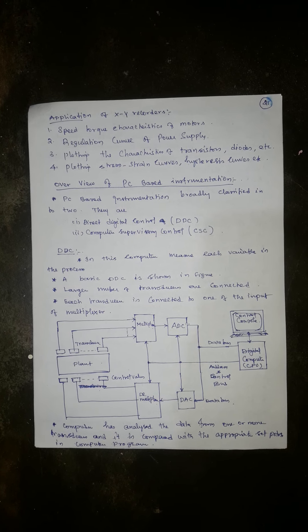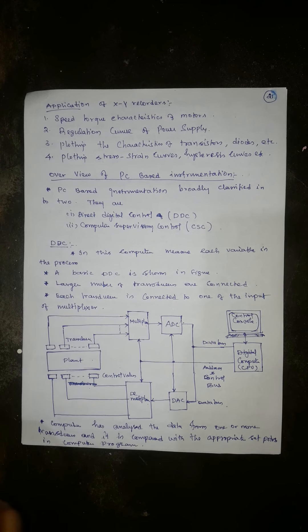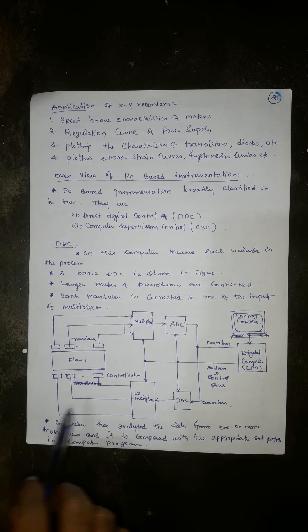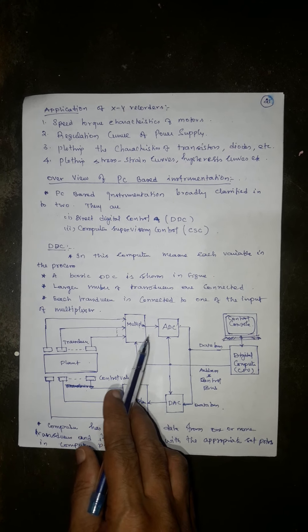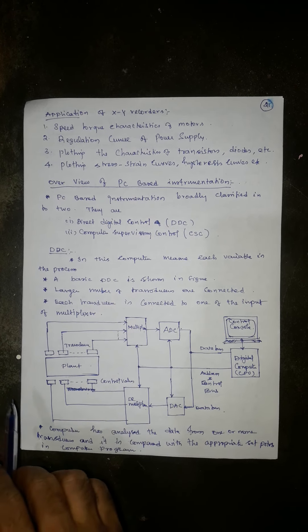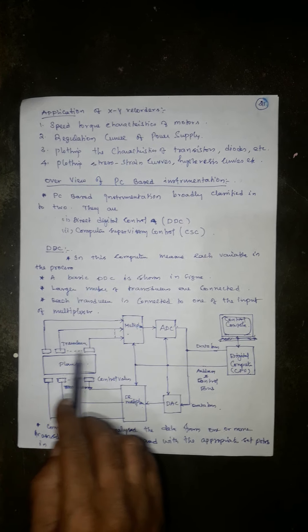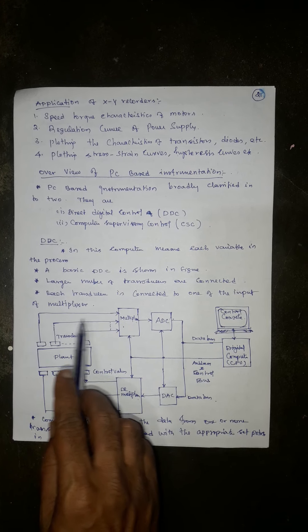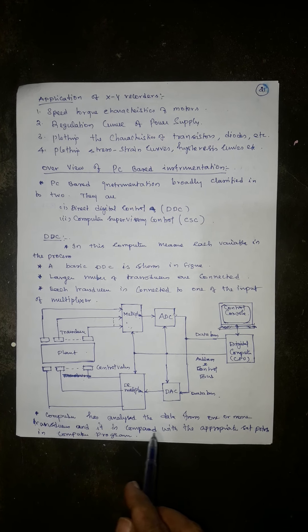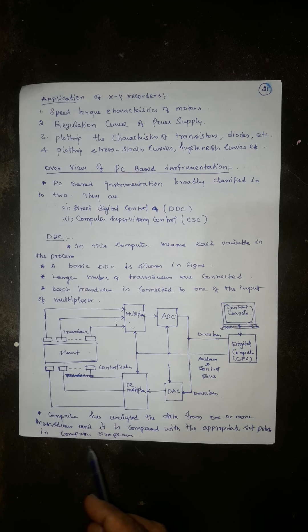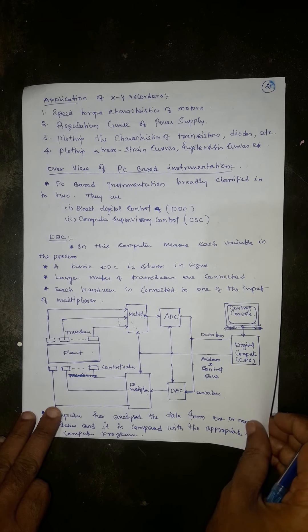In Direct Digital Control, the computer measures each variable in the process. A basic DDC is shown in the figure. A large number of transducers are connected, each transducer connected to one input of the multiplexer. The computer analyzes the data from one or more transducers and compares it with the appropriate set points in the computer program.